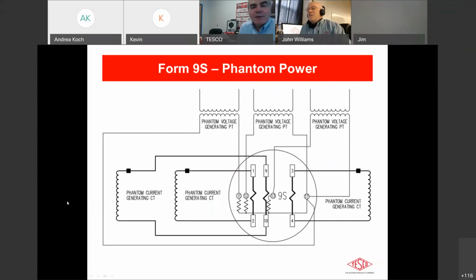What about, Kevin, you were talking about some of your 4S applications earlier and where they're still using those. Yeah, we talked about the 4S with the smaller restaurants that don't need three-phase air conditioning loads, using air conditioning on a single phase. The other one is large ranch houses that we talked about. So down here, we use a lot of 4S and 9S meters. Okay, good. And again, simple application from the test board side of things. We just have the 3 potential transformers, 3 current transformers into the meter socket.